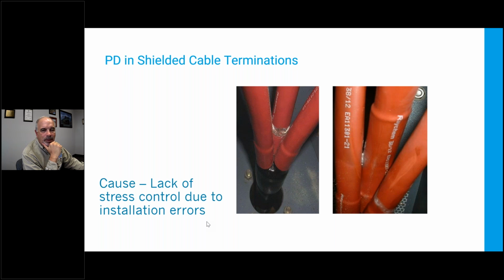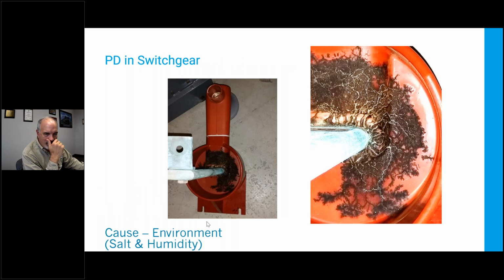User error here. Here's an example from one of my island customers. The poor guys are very close to the water. They have lots of salt and a lot of humidity, and this is not very old switchgear. It's very new. I took this picture myself. It was in a pile of other things that they had replaced. Tracking, treeing, you see the white powder. You see the copper has also turned a lovely shade of green.